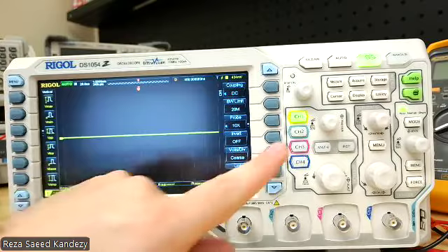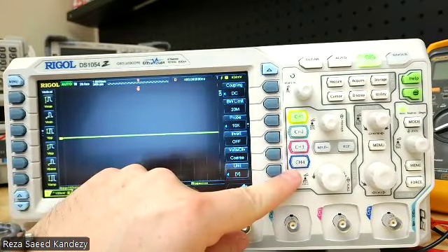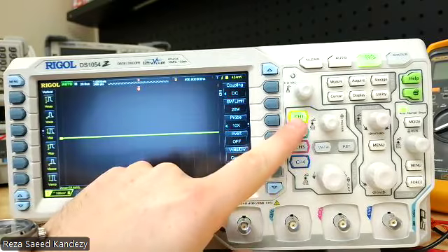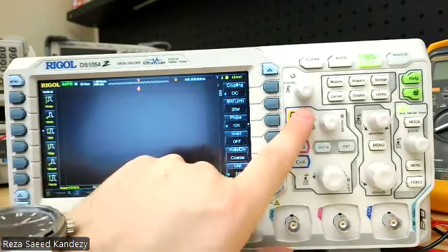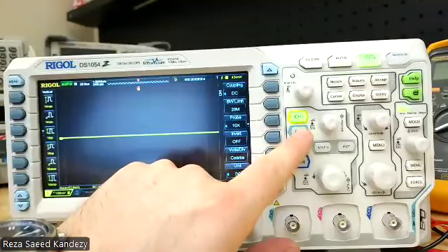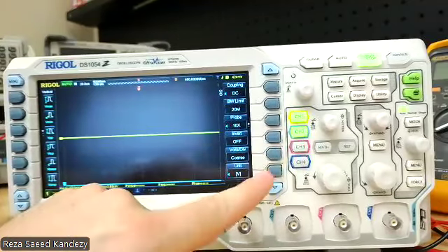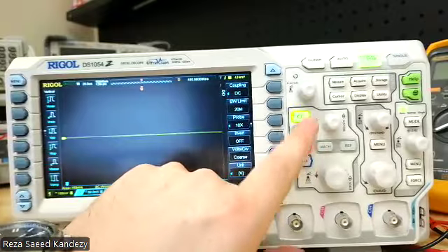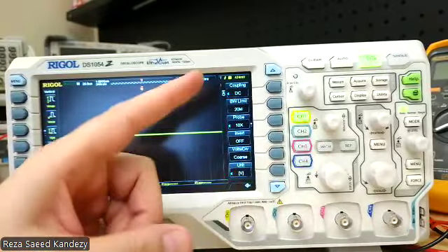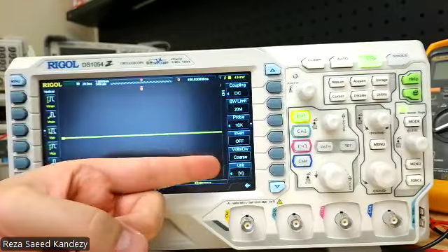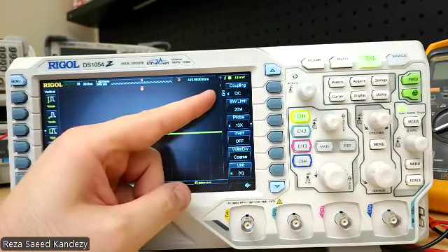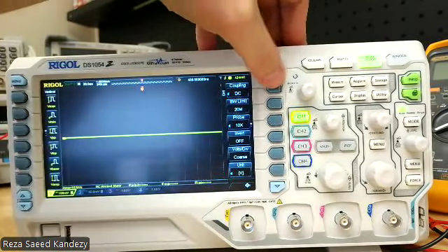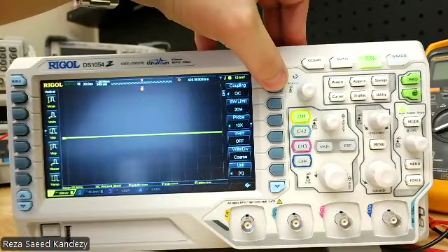Now, you can activate all those channels here, and you see I deactivated channel 1. If you push each of those channels, you can activate each channel, and it would open up a menu here, as you can see, that shows the characteristics of our system. Now, one of the options is coupling. With the button in front of it, you can control and change it.